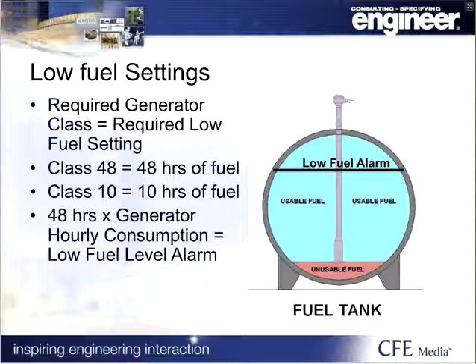The one little quirk here, which I like to point out, is that typically your fuel tanks have a piece at the bottom that is unusable fuel because of the way the tanks are set up. You can never pump that fuel out. So your low fuel alarm actually has to be 48 hours of the generator runtime plus the unusable fuel. You have to include that because it doesn't count. So just a little quirk to keep in mind.